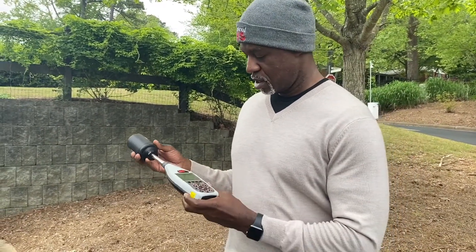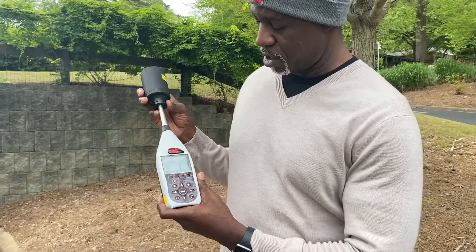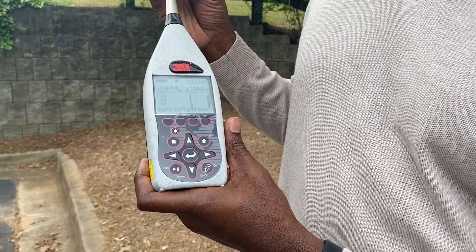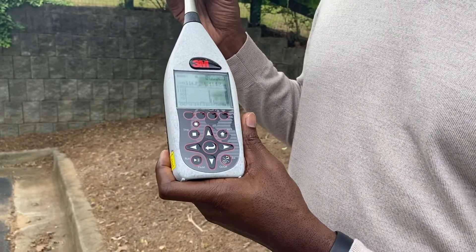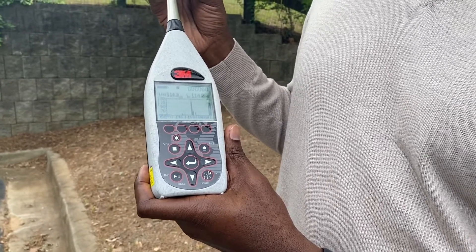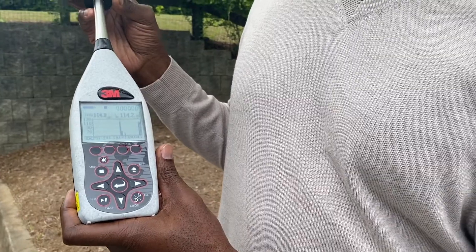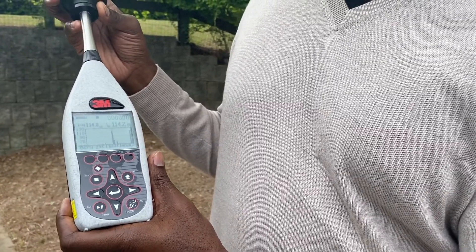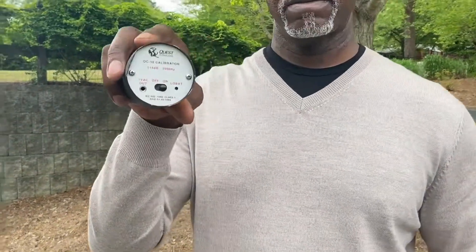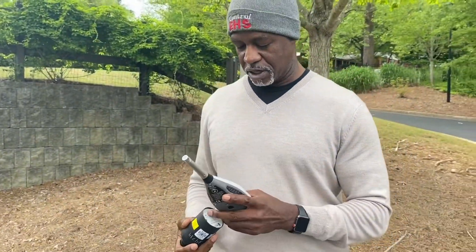An important thing about calibrating this instrument — we want to make sure that it has a known standard that we can reference. Here I put the calibrator on the mic and we want to look for something between 113.7 decibels and 114.3 decibels. Typically we want to have a plus or minus range of 0.3, and it is calibrated for 114 decibels. So that lets us know that the instrument is in calibration.